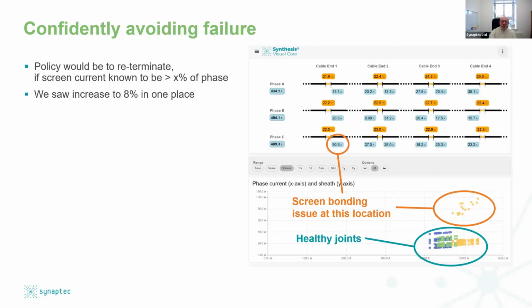So we were able to instrument all of those joint bays, each individual phase. So what is the phase current? What is the screen current? What's the relationship between the two of them? And have we got deviations? And very often it's the rate of change, or the rapidity or the amount of deviation that matters. It's not the absolute measurement, it's the change in the relationship.